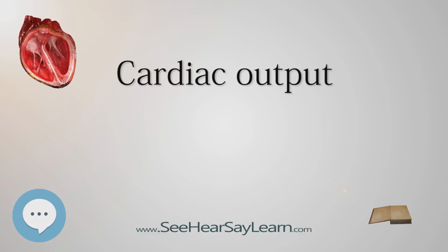Calibrated PP: PiCCO and LiDCO. PiCCO, Pulsion Medical Systems AG, Munich, Germany, and PulseCO, LiDCO Ltd, London, England, generate continuous Q by analyzing the arterial PP waveform. In both cases, an independent technique is required to provide calibration of continuous Q analysis, because arterial PP analysis cannot account for unmeasured variables such as the changing compliance of the vascular bed. Recalibration is recommended after changes in patient position, therapy, or condition.